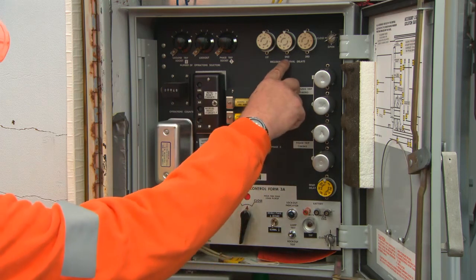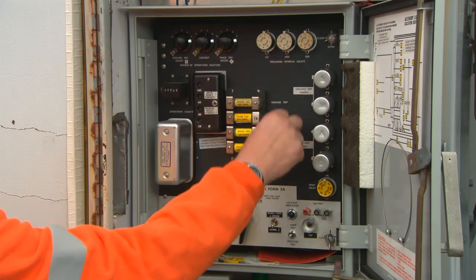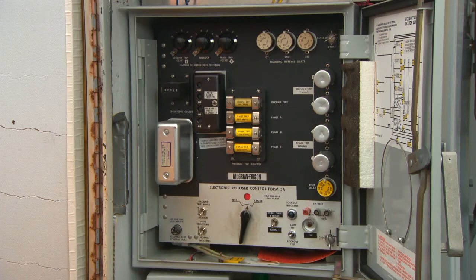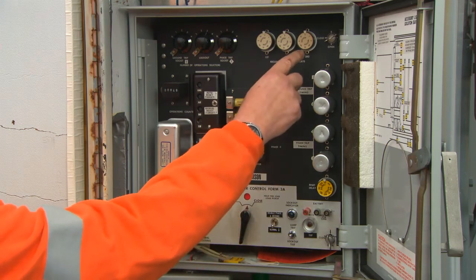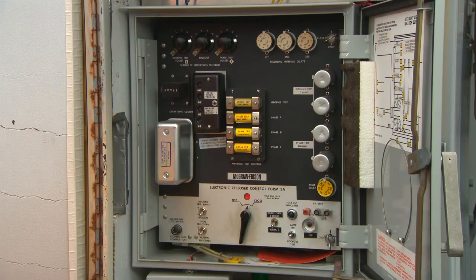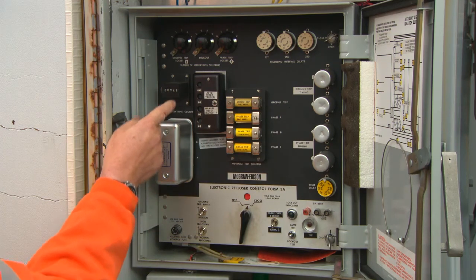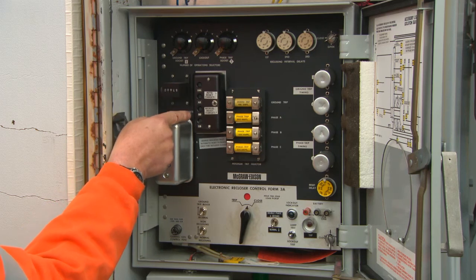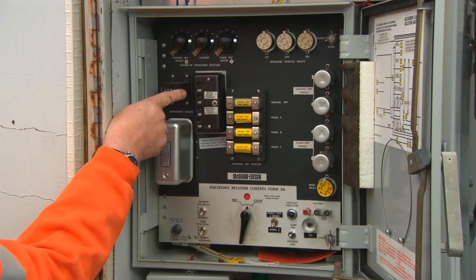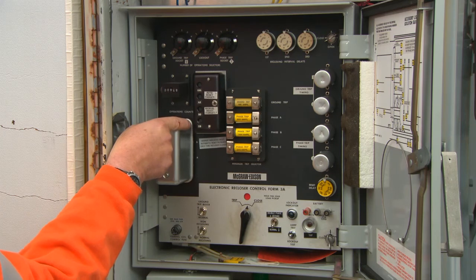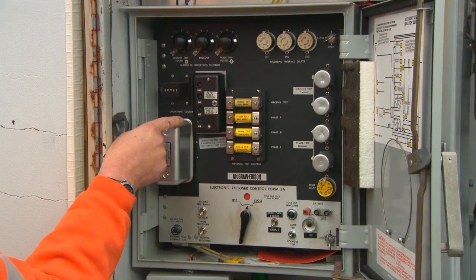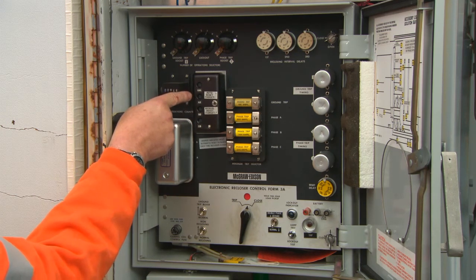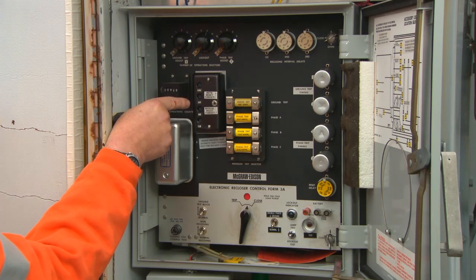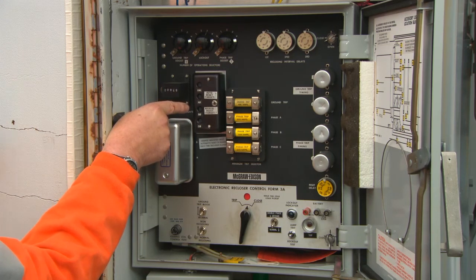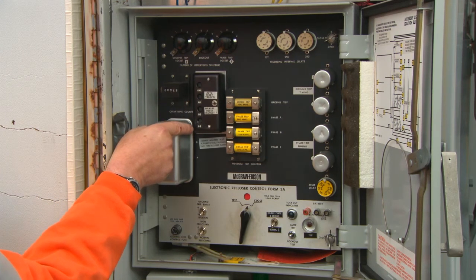Reclosing interval delays. When the recloser opens, there will be a dead time before it recloses. All 3 of these are set for 2 seconds of open time. Below these, we have the target indicators. This has status indicators for ground, A phase, B phase, and C phase. Upon tripping this recloser and when set for auto reset, these will display while tripping. Upon lockout, this setup will remain. By moving the toggle switch to manual reset, you can reset these targets.